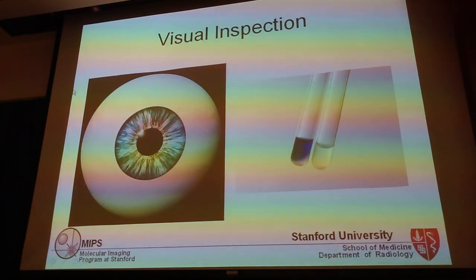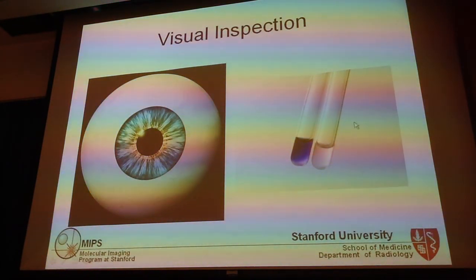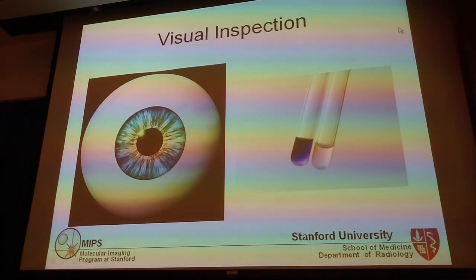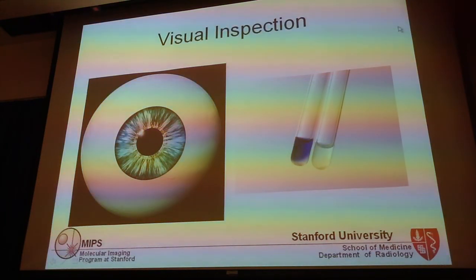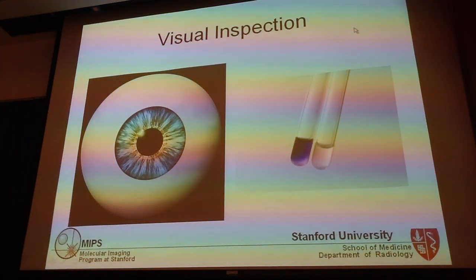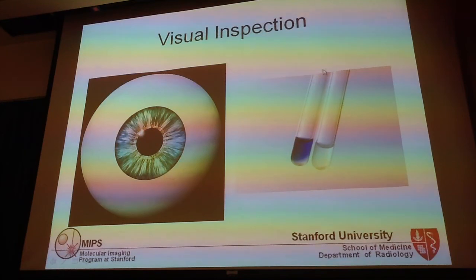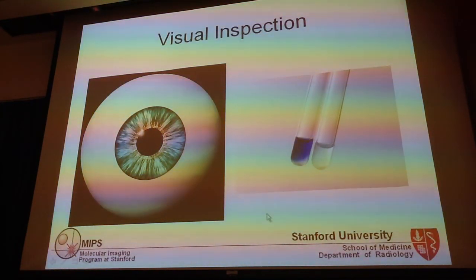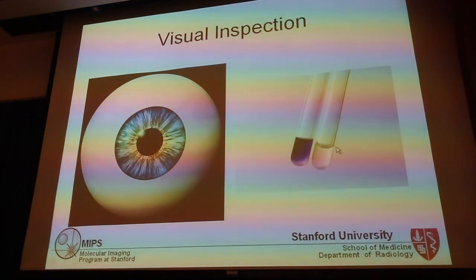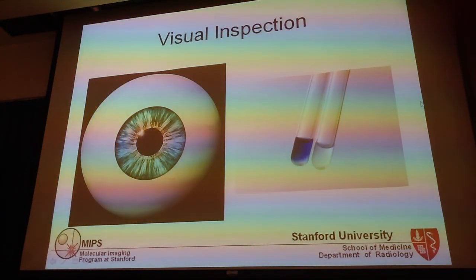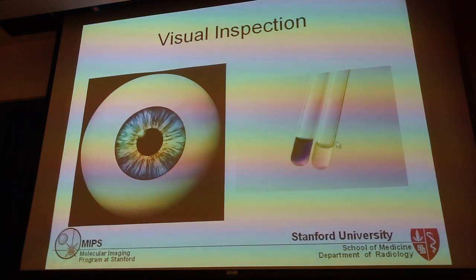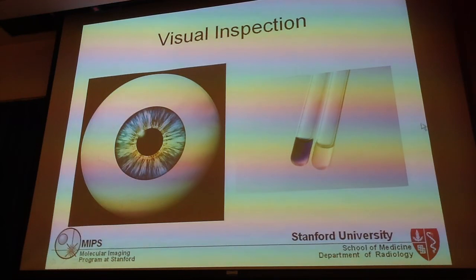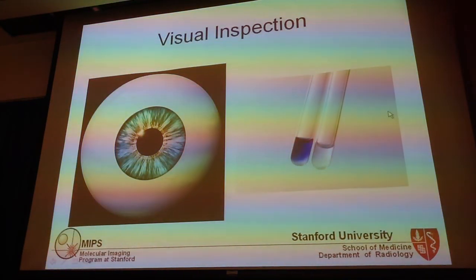The other thing is, as you remember, you do a visual inspection, hopefully behind the L block. Remember your L block? That's your radioactive or radiation protection glass. Most of our solutions are clear, so you shouldn't see anything at all. The only exception is what? Okay, MAA should look cloudy. But if it has any other colors than that in there, then you got a problem.